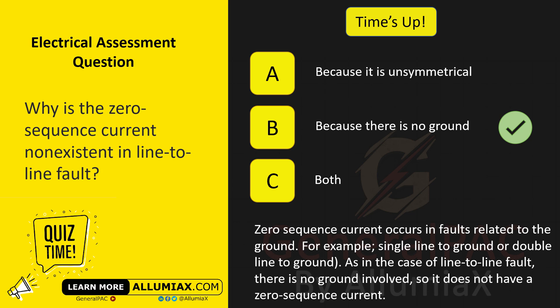Zero-sequence current occurs in faults related to the ground — for example, single line-to-ground or double line-to-ground. In the case of line-to-line fault, there is no ground involved, so it does not have a zero-sequence current.